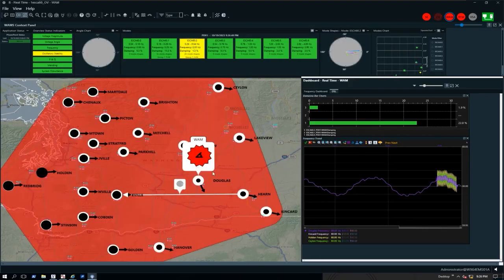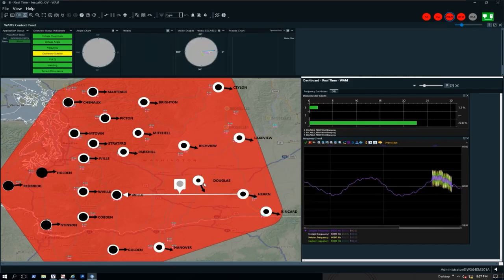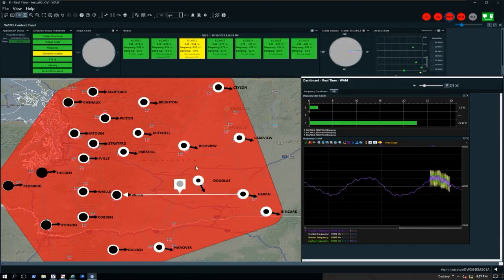So you can see here our frequency indication is already, our oscillation is already kind of dropped off, but we've got our different oscillatory modes. So this fill of the circle is the amplitude of the oscillation. So the amplitude at Douglas is very small, but very far away, like the ripple on a lake, you're getting large frequency and power oscillations. And then the arrow is the oscillatory mode. So we're seeing a large oscillatory mode deviation. That's telling us that Douglas is the one that's giving the most energy to this oscillation on the grid.